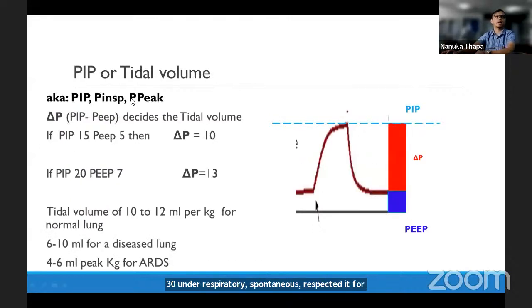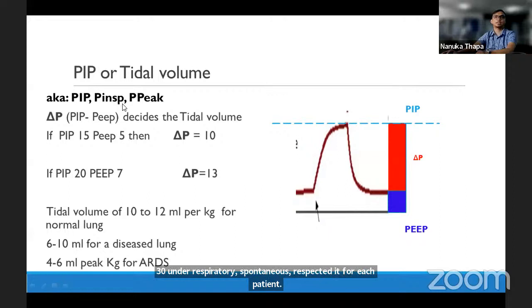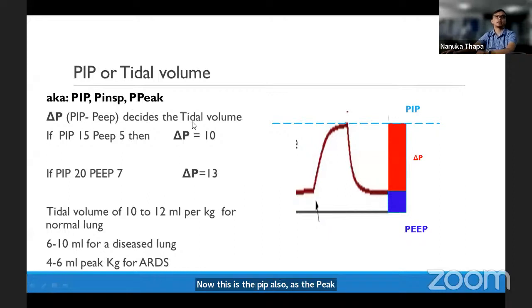Now this is the PIP, also known as the peak inspiratory pressure or the peak pressure. Delta P decides the tidal volume. How to calculate the delta P? It's peak inspiratory pressure minus PEEP. If we set PIP 15 and PEEP 5, then the delta P is 10. Same thing, if we set PIP 20 and PEEP 7, the delta P is 13. So in pressure control, the delta P will determine the tidal volume.